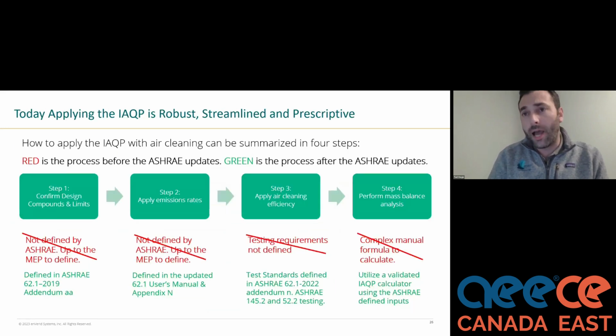I also want to talk about the IAQp and how it's become so much more robust. So previously, when you looked at the ASHRAE 62.1 indoor air quality procedure, when you were looking at your ventilation rate number, 0.06 CFM per, all those types of things, and just using a table, there wasn't a whole lot of thinking involved. And then you went to the indoor air quality procedure, and a lot of the answers were, it's up to the engineer of record. Things like, what is an acceptable design compound and limit for things like formaldehyde? What's an acceptable limit of formaldehyde in an office building? Well, that's hard to know, right?